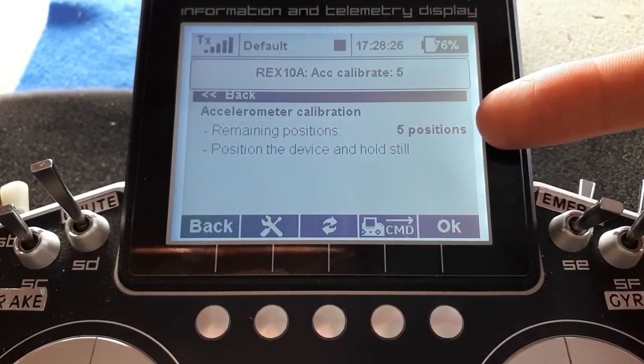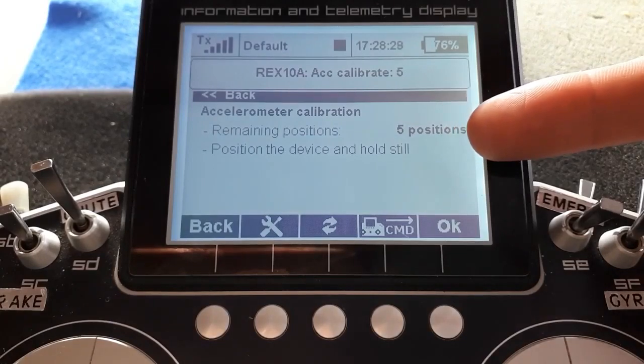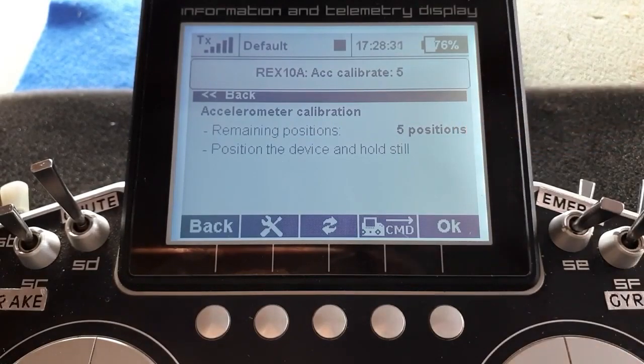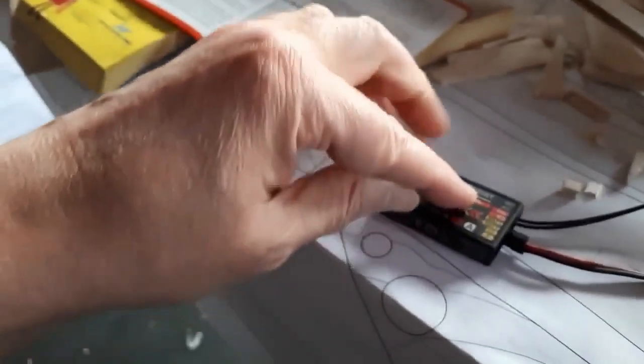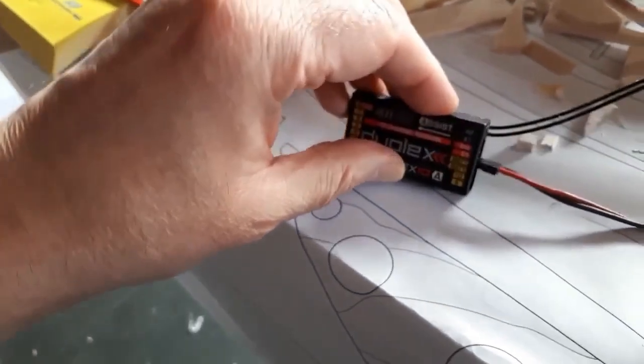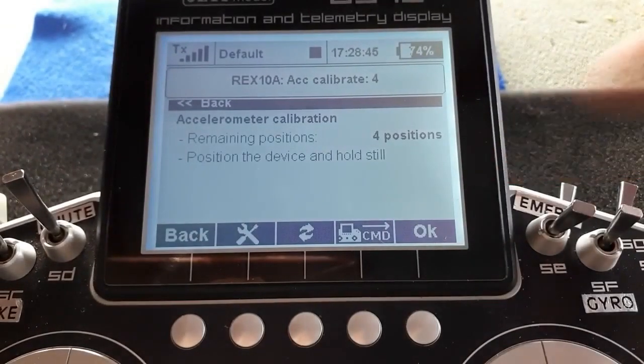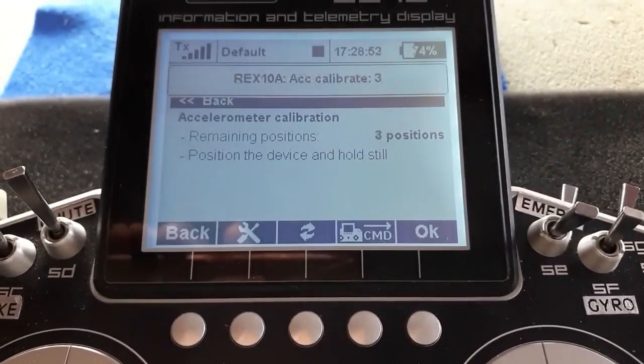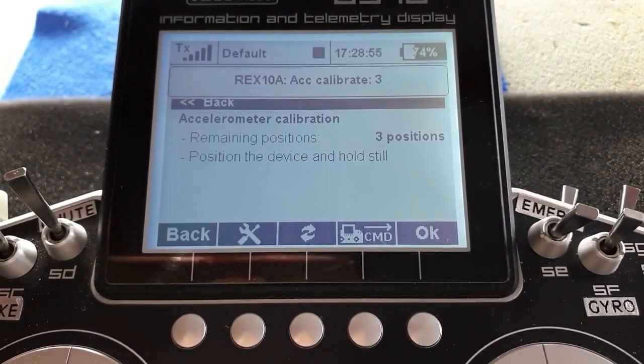Did you see that it said 6 positions? Now it's got 5 positions remaining. That's because it's now worked out the first position that it's on. Okay, I'm going to rotate it round 1 to that edge, flat on the surface. Calibration in progress. And she speaks, and now it only has 4 positions left to do. Turn it round again onto the face there. Calibration in progress. It's only got 3 left to do. I'll turn it again onto the next edge. Hold it still. Calibration in progress.